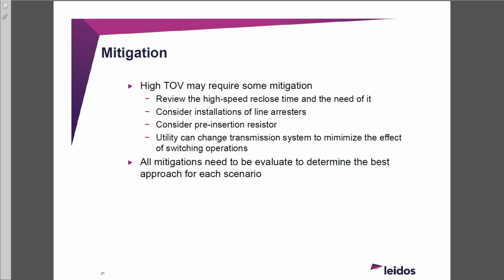Exactly, so it really helps, and you start adding it to your standard designs. We have a client that now makes this their standard package. One last thing: we really emphasize 500 and 230 kV, but because of high-speed reclosing, we've seen it used at 138 kV too, so the TOV jumped way up and became an issue for them as well, and that gave them headaches. Like you said, if there's no line arrester, that's when issues start.